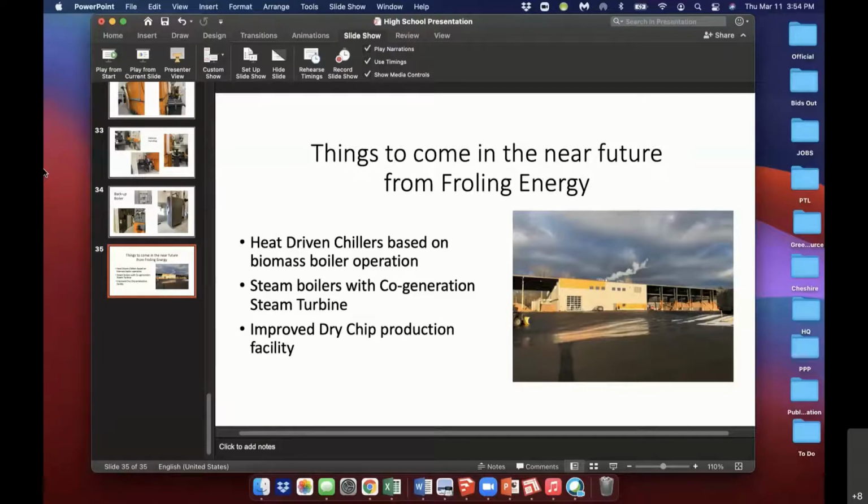So we take great care in choosing, looking at it, do we have a person that can really take care of it? Or do we need 100% automated operation that's really robust because we don't have somebody who can specialize in raking a grate? Because that's definitely an operation that, for instance, if you only have a janitor taking care of it in a school, which is quite normal now because schools have been having their funding taken away, so they're reducing staff, that's an unfair request to have a grate raked on a weekly basis by a janitor. That's an uncomfortable situation. So then you have to design it like, okay, let's get a moving grate in there, let's get full automation in there, make it more robust, and make sure that we have a boiler that only really needs to be touched twice a year, and then we can do that by service, but it will cost more.